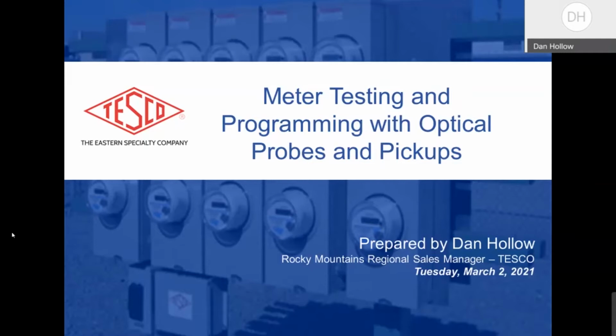Back at that particular time, there were something called box recorders. They were just a NEMA type enclosure with a board in it, and they counted KYZ pulses that came from electromechanical meters with pulse initiators in them, and then they'd feed those KYZ contact closures into a board, and those pulses would be counted. KYZ is just a single pole double throw relay, and back in those days they were mercury-wetted relays inside the electromechanical meters.